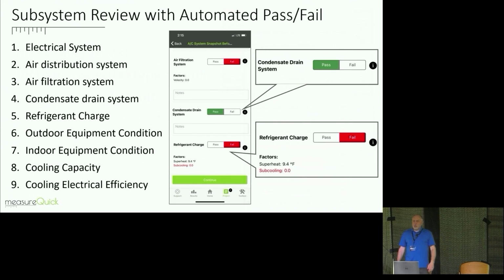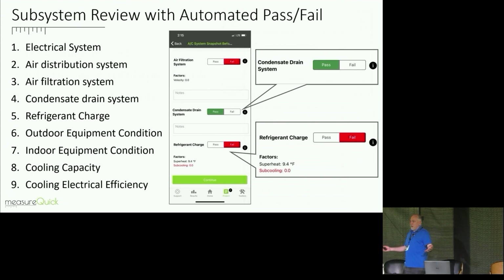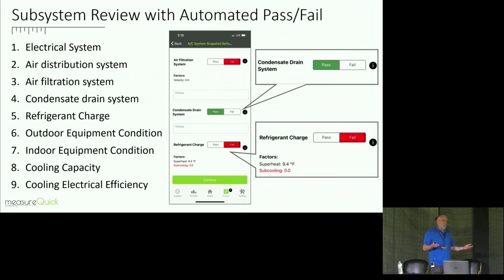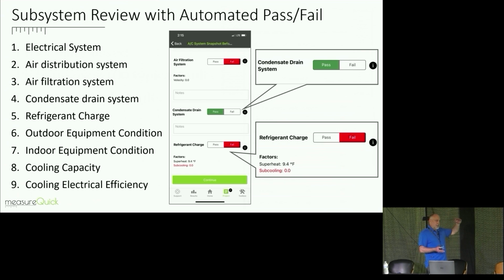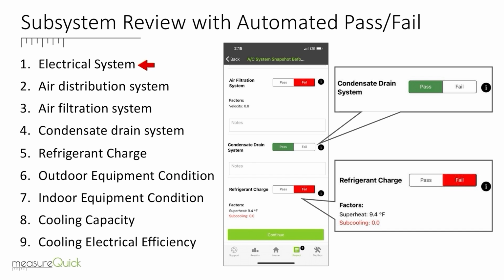Subsystem review. So after we figured out, hey, we got all these targets and we can do all this stuff, we found out, well, people were printing out reports that they were missing faults that we were seeing in there. So now we actually run an analysis on your electrical system. So I'm looking at your utilization voltage, I'm looking at your power factor, I'm looking at your air distribution system, your temperature split, your static pressures to make sure they're in right, your air filtration system to make sure the filter face velocity is right.